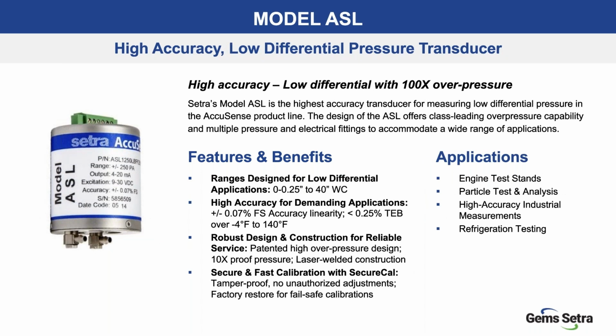This is followed by our AccuSense line of products. Model ASL provides low differential pressure measurement with a 100 times overpressure capability. That makes for a great differential sensor that can handle real-world overpressure applications, as we've seen. This product meets the low pressure requirements of 1/4 of an inch to 40 inches of water column, with the high accuracy demands of 0.07% full scale linearity and a very impressive 1/4% thermal error band over -4 to 140 degrees F.